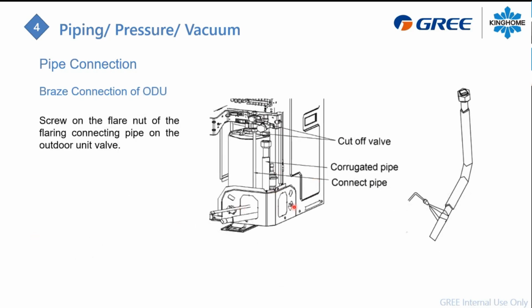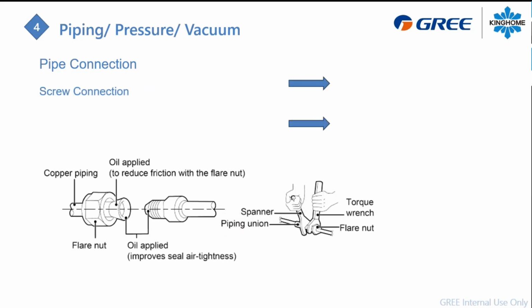On the outdoor unit, if it's a 2-ton unit, the connection is inside the unit, so you need to remove the panel to make a good bend in your piping right here. This is why the connection is already twisted a little bit. That will help you make your bend and move the piping out from the corner panel. But again, make sure you make a good connection here. Use your torque wrench also. This is really important.